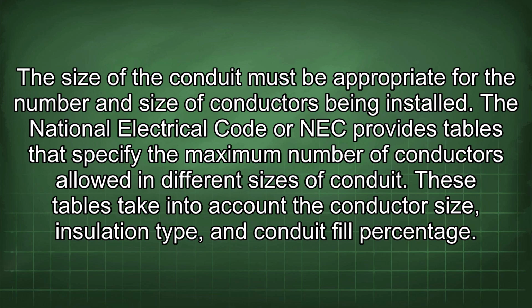The size of the conduit must be appropriate for the number and size of conductors being installed. The National Electrical Code, or NEC, provides tables that specify the maximum number of conductors allowed in different sizes of conduit. These tables take into account the conductor size, insulation type, and conduit fill percentage.